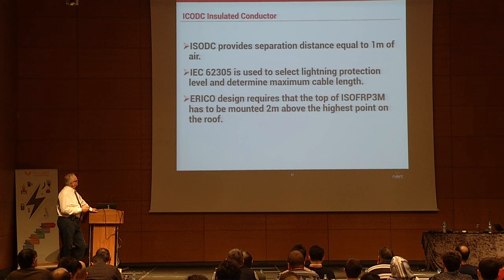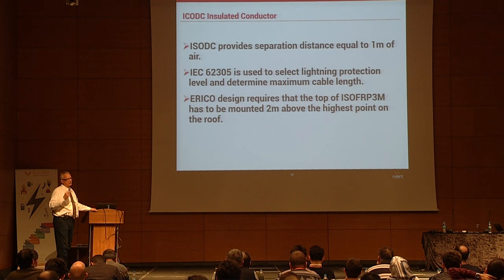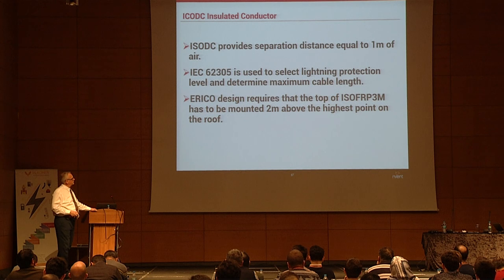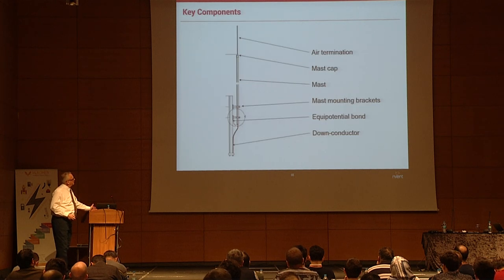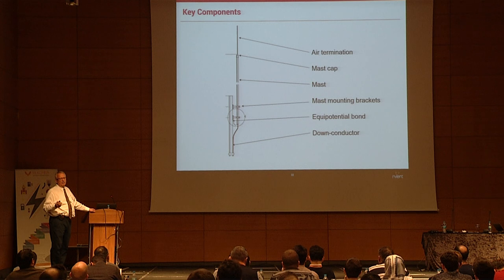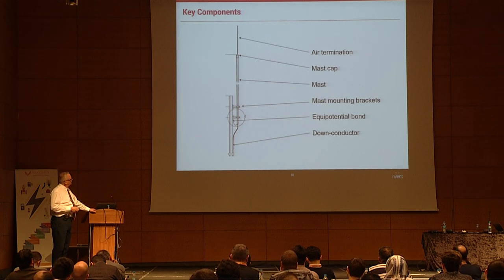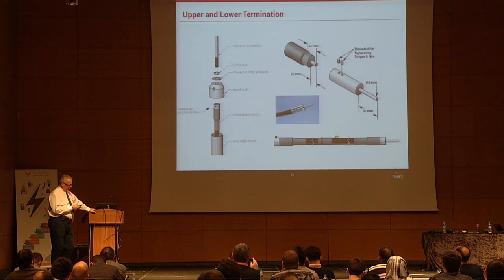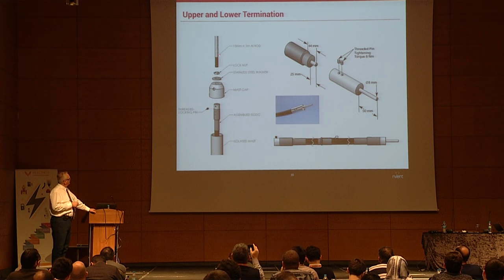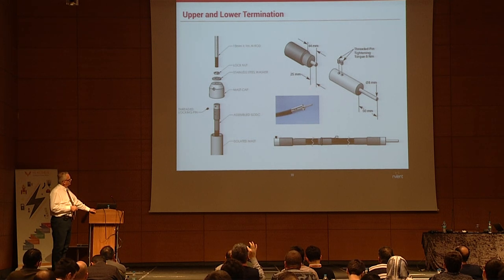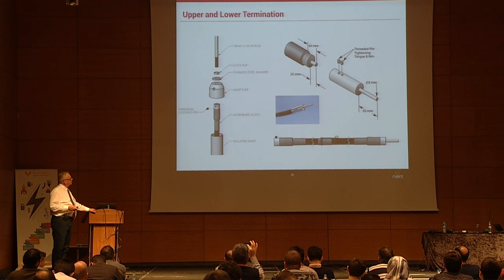Some highlights: the terminal must be placed at least two meters above the highest point on the structure. This is the full system — not just the cable — it includes a mast, upper and lower terminations. The rod couples into the cable itself, and the lower termination connects to the grounding system. We have third-party certification for the system.